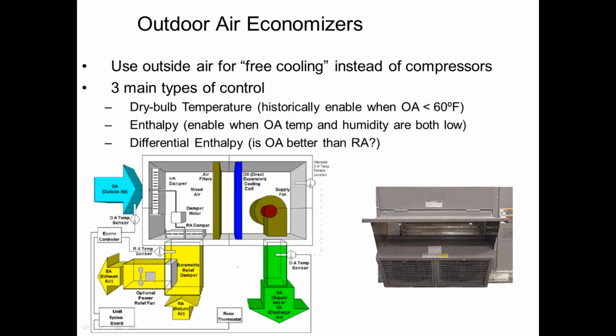So on mild days, I want to use the outdoor air to free cool. There are 3 main ways we have done that historically for our climate zone. Dry bulb temperature, which means I don't care how humid it is. If it's below a certain number, use the economizer for cooling. 60 was a pretty common number we used to use back in the day. If it's below 60, open the economizer for free cooling. If it's above 60, run your compressors.